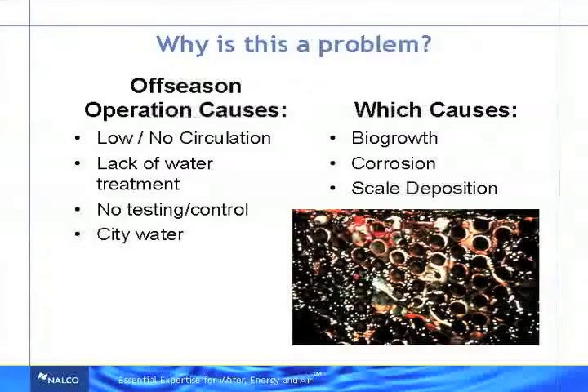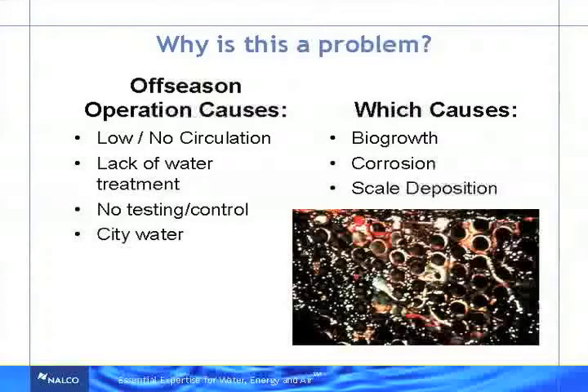So what you'll get is a large influx of city water. When are you going to inspect your condenser bundles? Off-season. So that's 3,000-4,000 gallons of water goes down the drain. You replace it with fresh city water, and that can cause some problems. The problems you're going to see, which Mike's covered pretty well here, but they tend to intensify a little bit in the off-season, are biogrowth, corrosion, and scale deposition. Here's an example of a tube bundle of high biogrowth in the off-season because they just let it sit there. Then when they went to do the inspection, that's what you found. So that's why it's a problem.